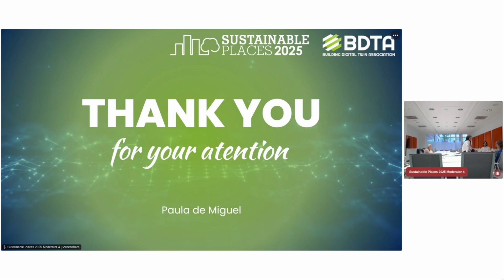Finally, the idea is to create a digital twin. So, for example, of the data center of the Barcelona supercomputer, the idea is that you can simulate with real data what is happening, and you read all the data from the real building in this case, and you simulate it. It's not sharing the elements, but you have your simulator in real time, and you can discover an error that you are not monitoring in the real building.